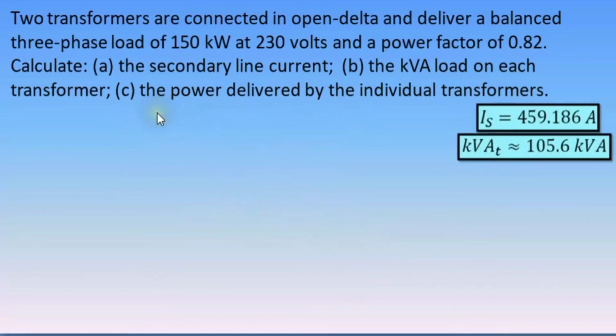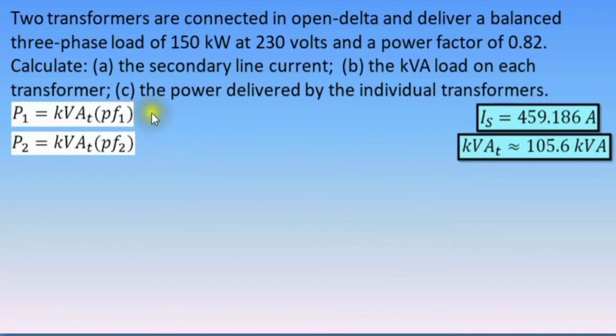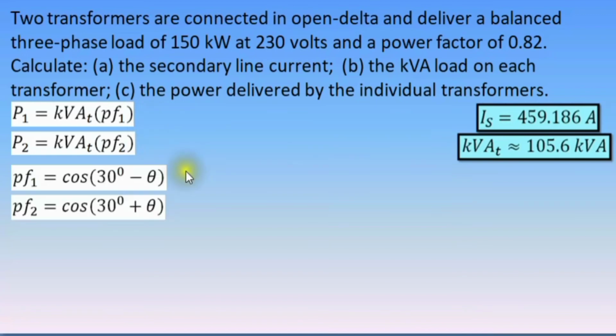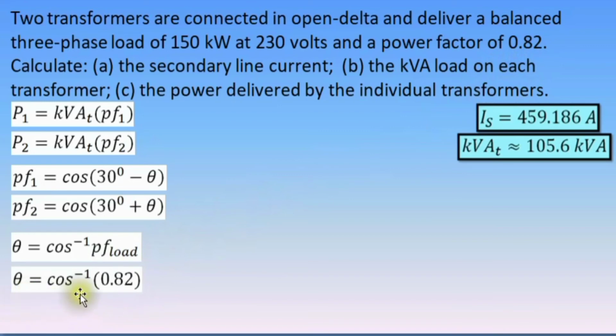Now let's go to letter C, the power delivered by the individual transformers. To determine that, we use this formula. Again, this is just simple apparent power times power factor. But of course, we first need to determine the power factor of each transformer. So these are the formulas that we are going to use. And of course, we need to determine first the power factor angle of the load. Using this formula, the power factor of the load, that is 0.82, substitute that. So therefore, theta equals the inverse cosine of 0.82. Theta is equal to 34.915 degrees.